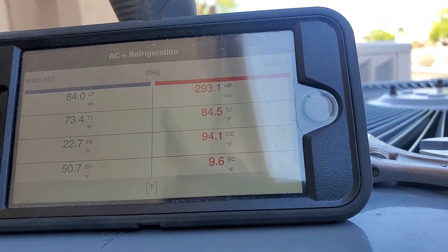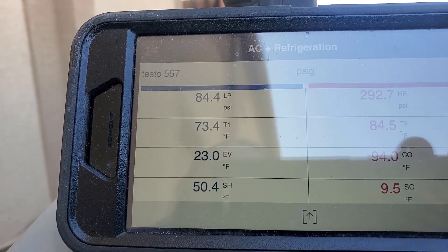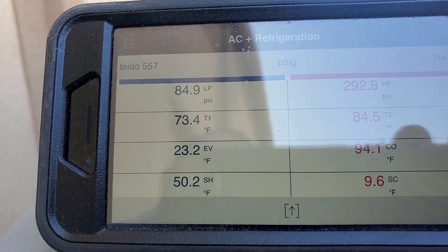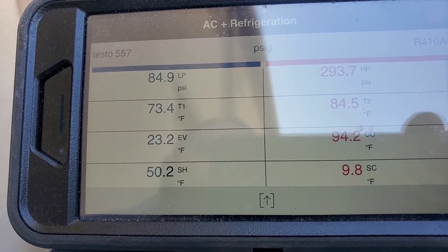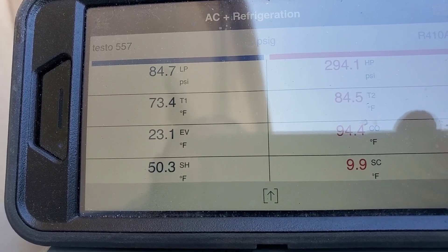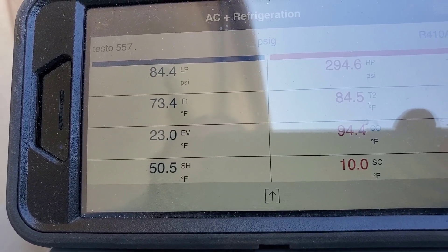About 9 degrees subcooling — almost 10. We've got enough refrigerant there. Looking at the superheat and suction pressure, it seems like the TXV is not feeding enough refrigerant. It is a long line set, but the suction should probably be a little bit higher. It's probably doing something — I'll go over with the infrared and probably read something eventually.